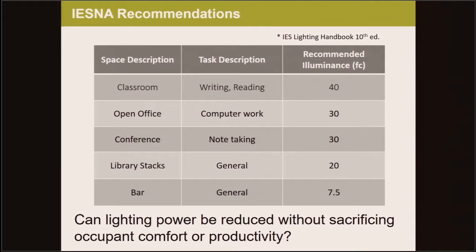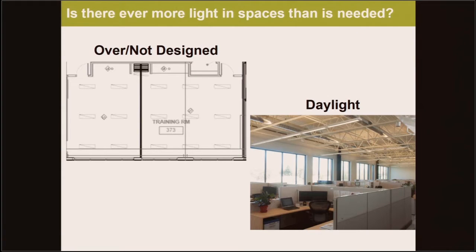So now we need to understand if there's ever more light in a given space than is actually needed. It turns out the answer is usually yes. A recent study I conducted found that commercial spaces were on average overlit by up to 20%. In many buildings, there isn't much thought put into the lighting design, as a contractor simply puts the same fixture on a uniform grid, project to project, without analyzing how much light is actually provided. When a lighting designer is involved, there's a much greater chance that the lighting illuminance will be more appropriate and in line with recommended levels.